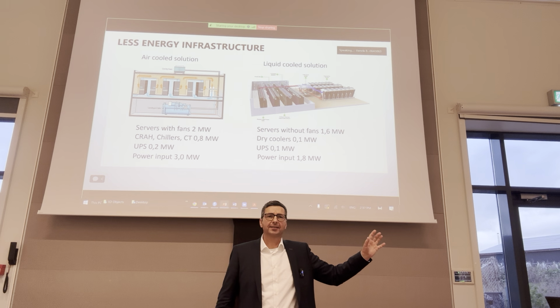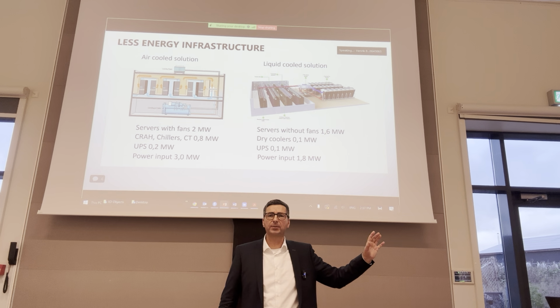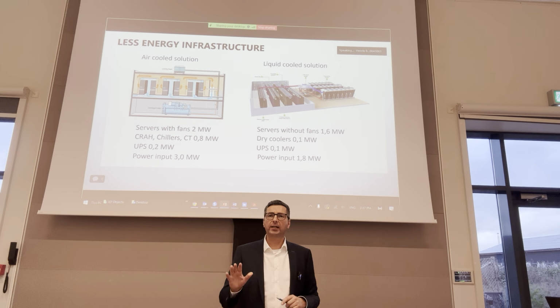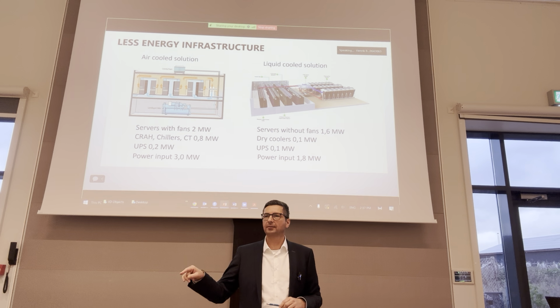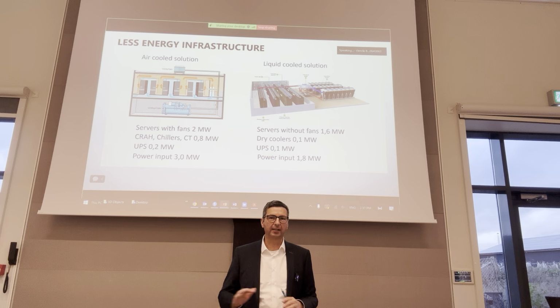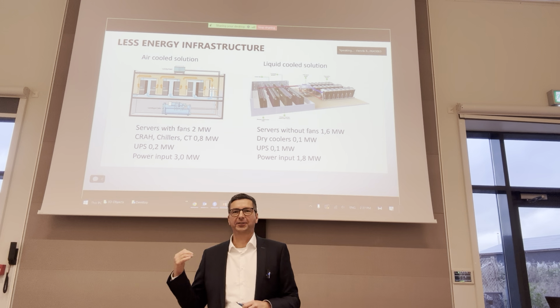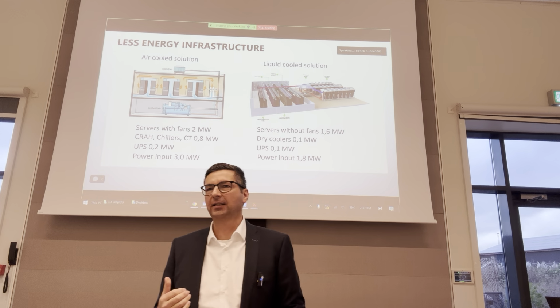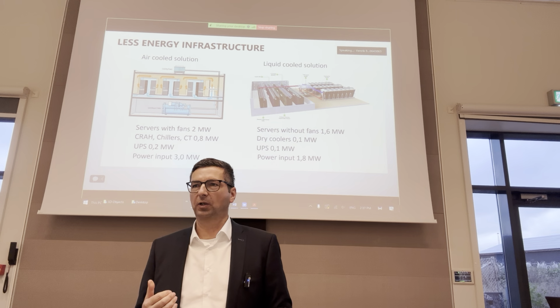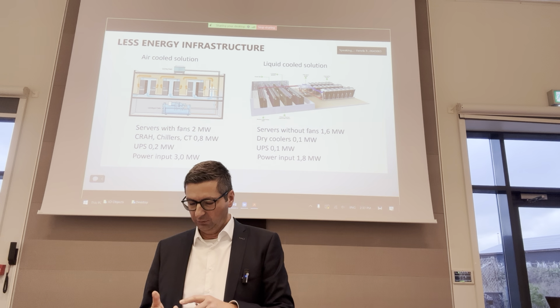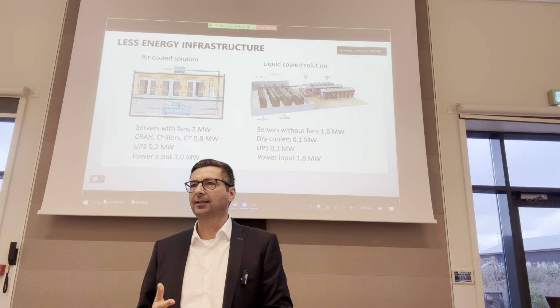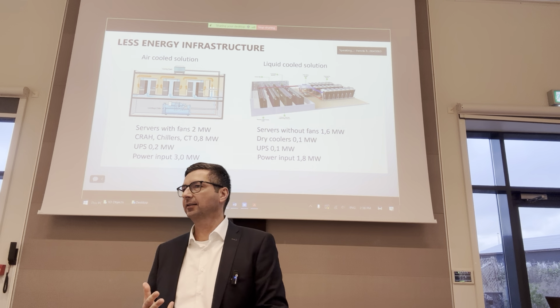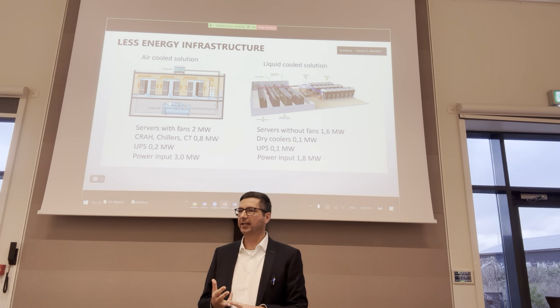On the liquid-cooled side, you can see it's 400 kilowatts less because of the missing fans in the servers—straight away 400 kilowatts are gone. In the traditional legacy setup, you'll need 800 kilowatts for the air chillers and cooling towers—really, 40% goes into the IT load there.